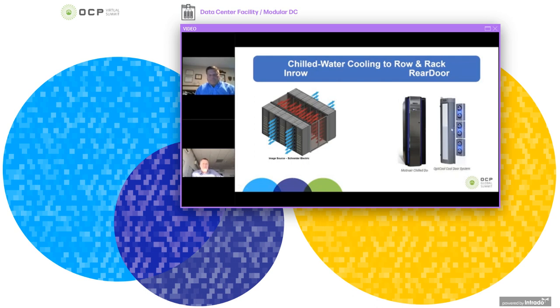So what we've got here is what we call water cool type cooling, where we're using in-row coolers on the left with an aisle containment. The IT goes in the middle, the in-row coolers pull the heat out and blow cold air out. On the other side you've got the rear door, which acts like a big radiator at the back, pulling the heat out of the IT and drawing it front to rear. In both cases it's actually a water-based solution that works.